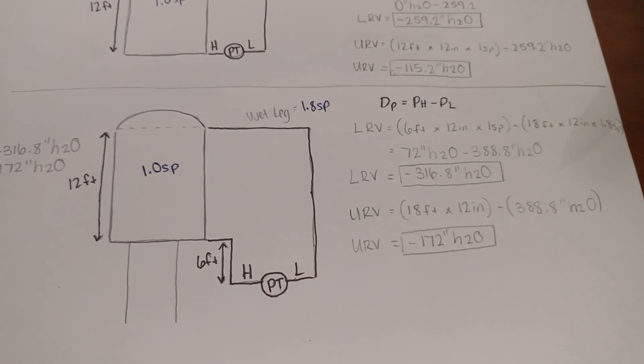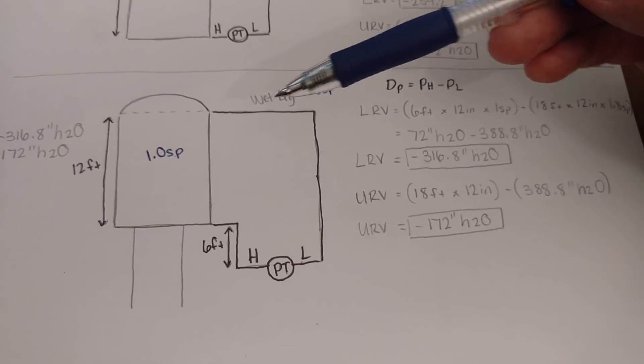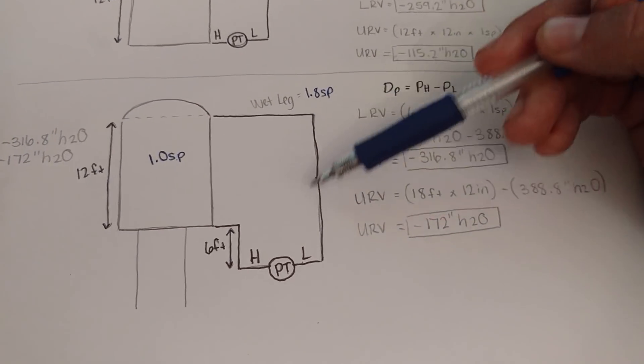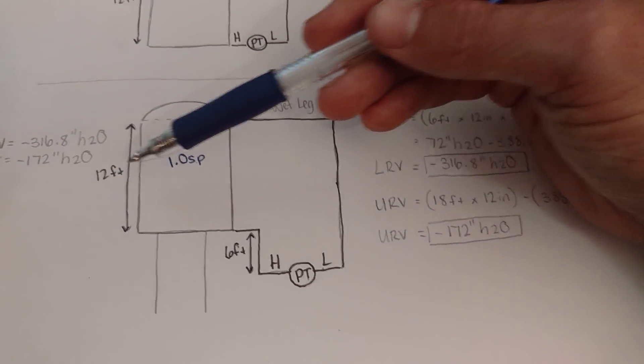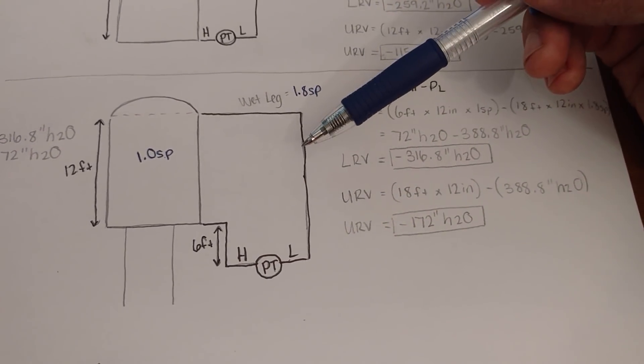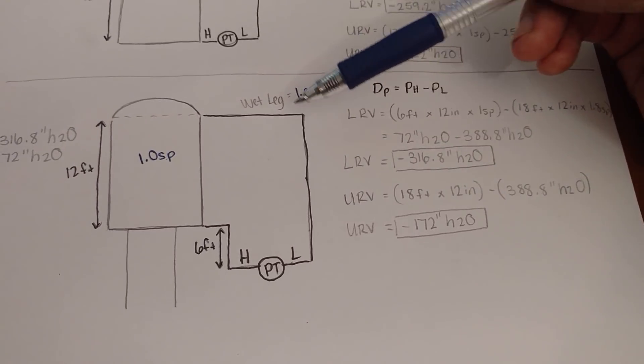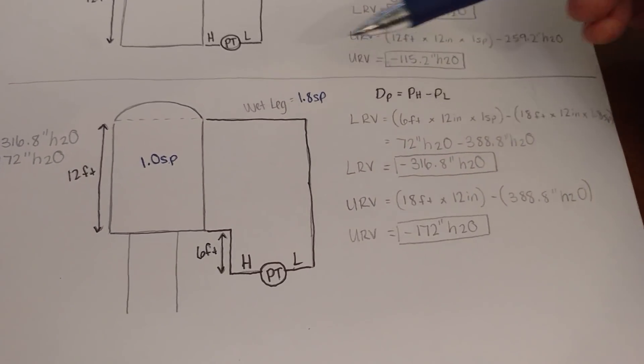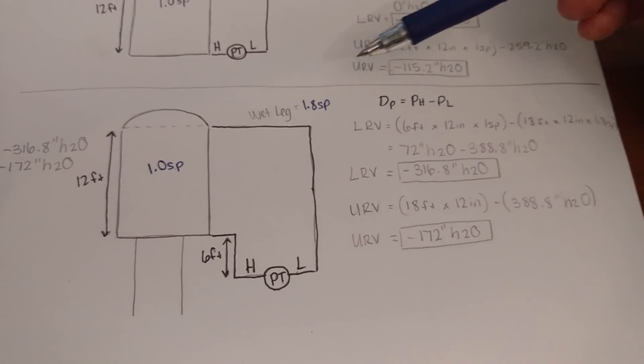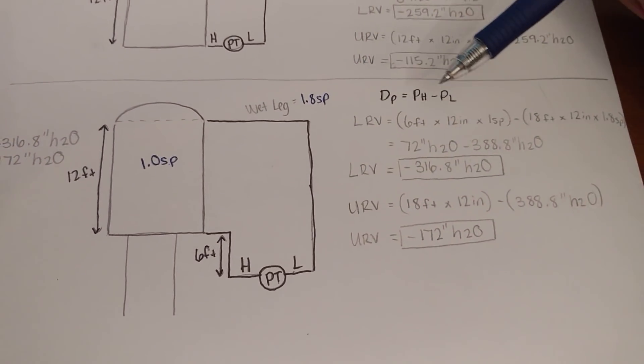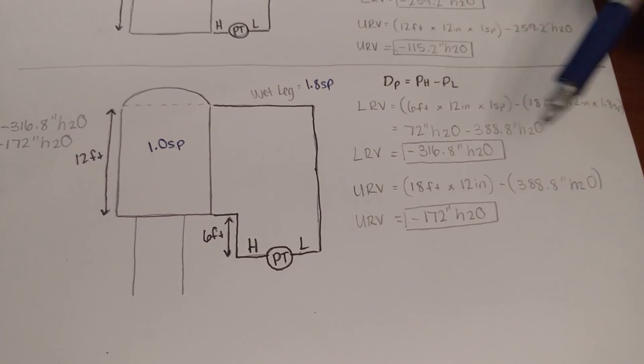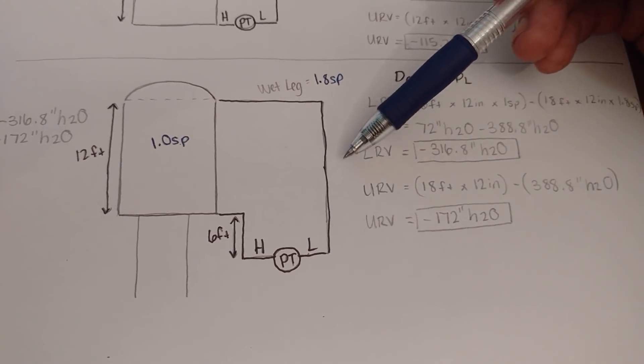Our pressure low is going to be 18 feet, because the entire pressure low side spans 12 feet of tank plus 6 feet below — that's 18. So: 18 feet times 12 inches times 1.8 specific gravity gives us our hydrostatic pressure for the low side. Pressure high minus pressure low gives us negative 316.8 inches H₂O. We're done with our lower range value.